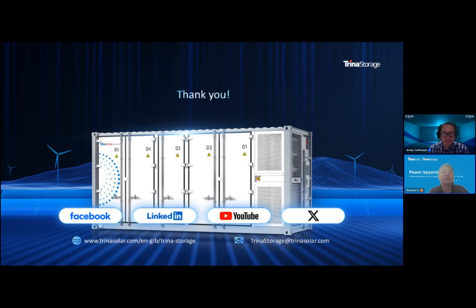Thirdly, the 4 megawatt hour unit shall be integrated by having all the battery interconnection cabinet into the battery container. So there will be no extra cabinet for the 4 megawatt hour unit. But for the 5 megawatt hour unit, you have to install another small cabinet in order to provide the combining bus bar and also the protections on the combining side, as well as the communication functions, communication devices for the BIC for the single cabinet. So these are the 3 major differences behind the two products.